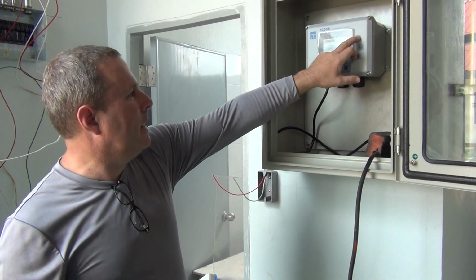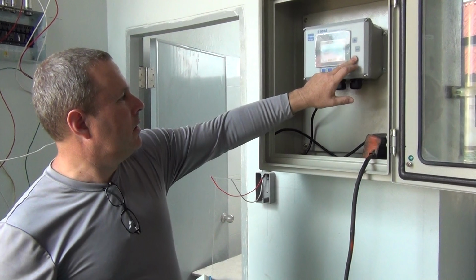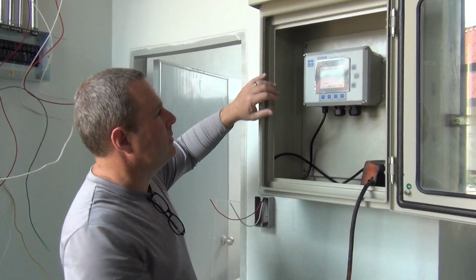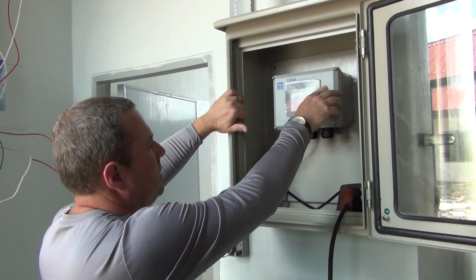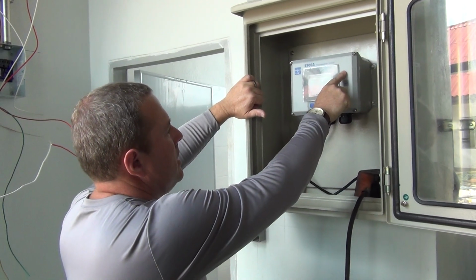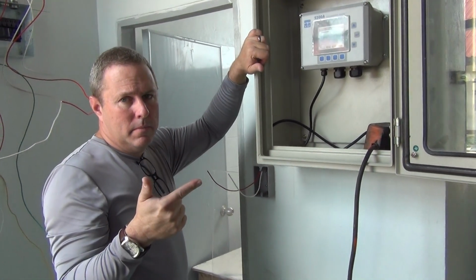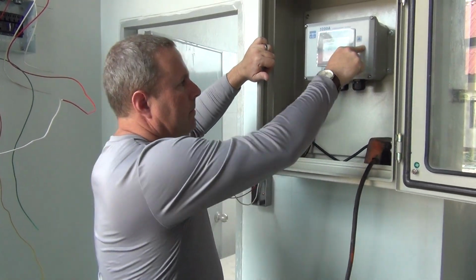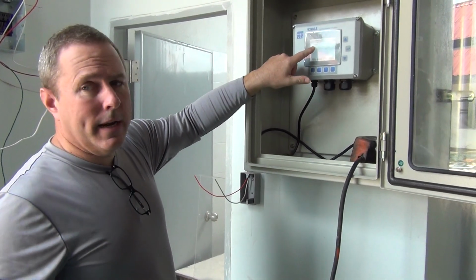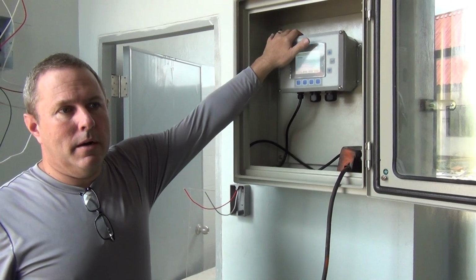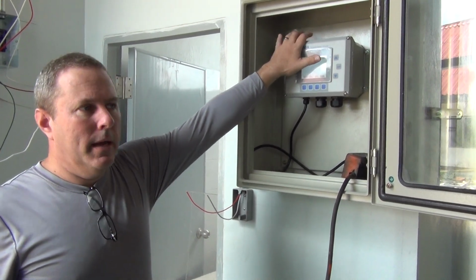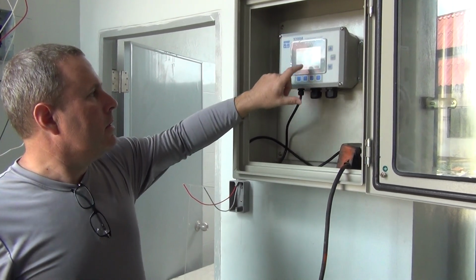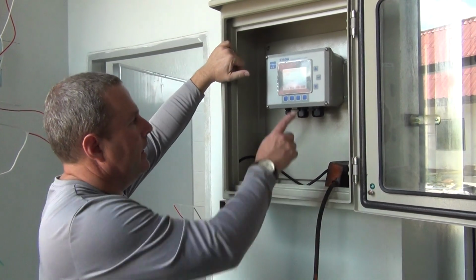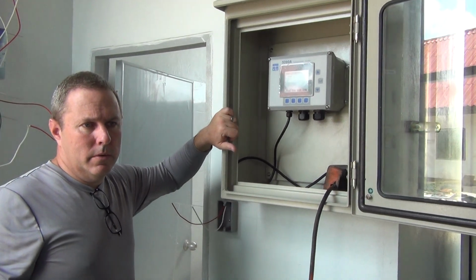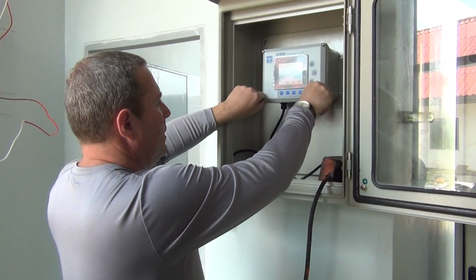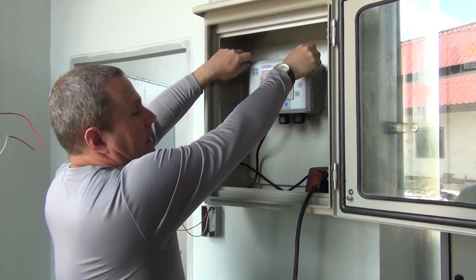I need to find my network, which will be under communications. So under menu, system, communications. So here I can set the Ethernet address. This is also part of an RS-485 network controller. It can be a master or slave of multiple units. So if I were doing that, I would set that here. It can also work with a serial port, RS-232. So if I wanted to run RS-232, I would set the baud rate and the settings here for interfacing.